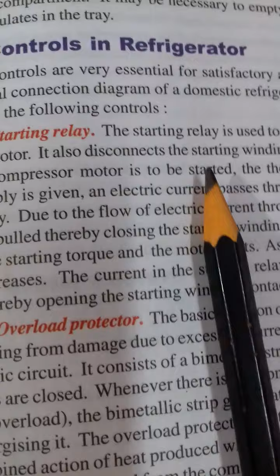The electrical connection diagram of the domestic refrigerator is shown in the figure. The refrigerator is fitted with the following controls. Starting relay, that is for the compressor motor. The starting relay is used to provide the necessary starting torque required to start the motor. It also disconnects the starting winding of the motor when the motor speed increases.